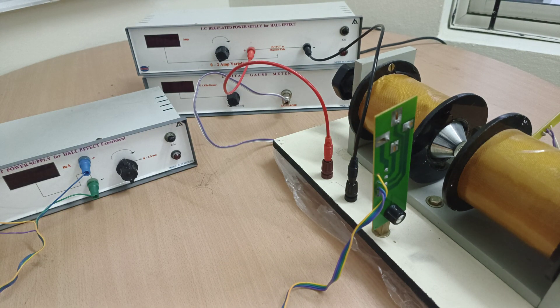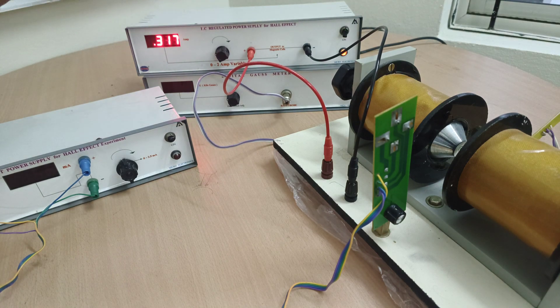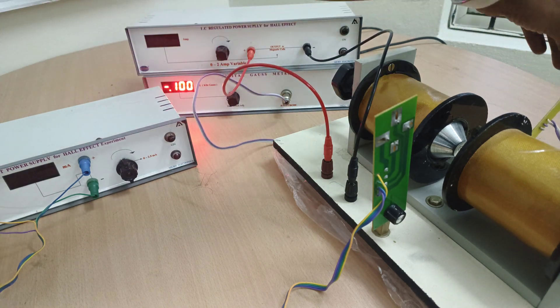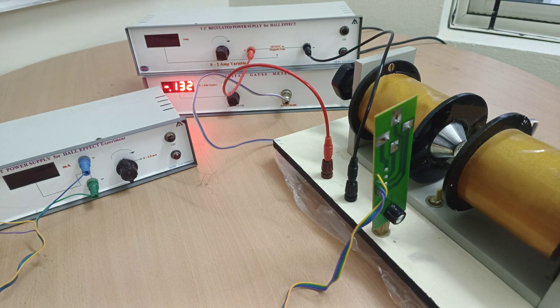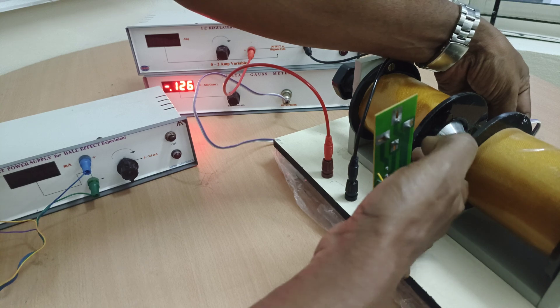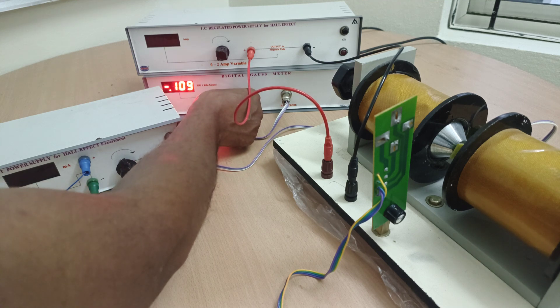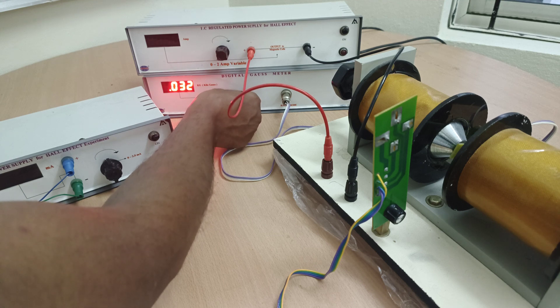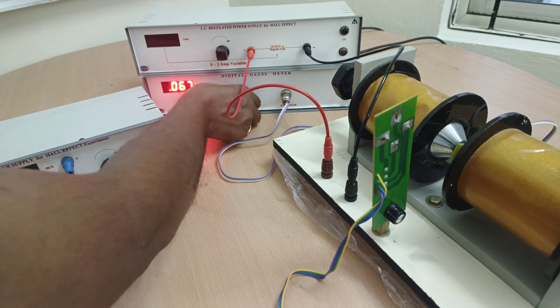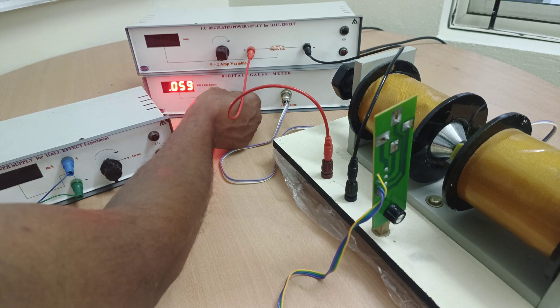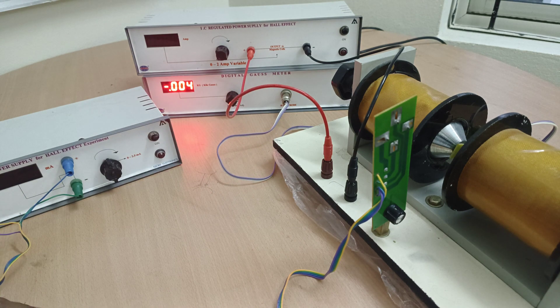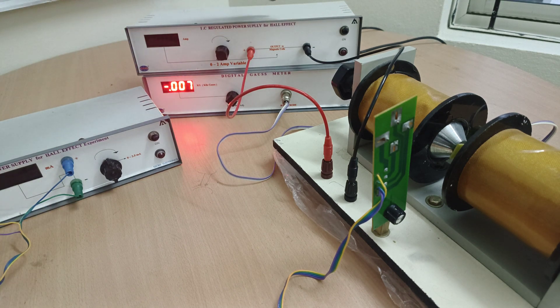Once all connections completed, switch on the power. Before that, switch on gauss meter and insert gauss probe exactly in the middle of the electromagnets and adjust the value, make it zero adjustment. This one is in kilogauss. Once it is completed, switch on the IC regulated power supply.